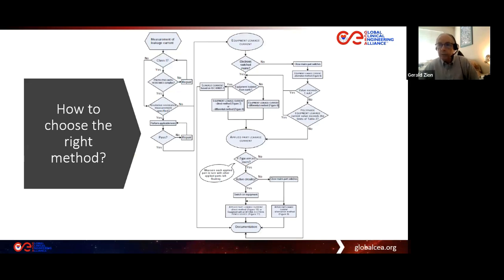The IEC 62353 uses three different testing methodologies. The direct method is the one most able to be correlated to the IEC 60601-1. And for that reason, a quality manager at a medical device manufacturer may want the field service engineers to use the IEC 62353 direct method as the way that they do the testing, except when there is a different method that would actually be required under the standard.